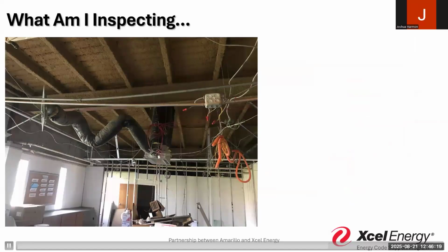If I see a 10-foot line or 10-foot equivalent length identified, and I've got a 20-foot long flex line like the one we see here on the screen, I'm really going to have that conversation that this is not going to work.